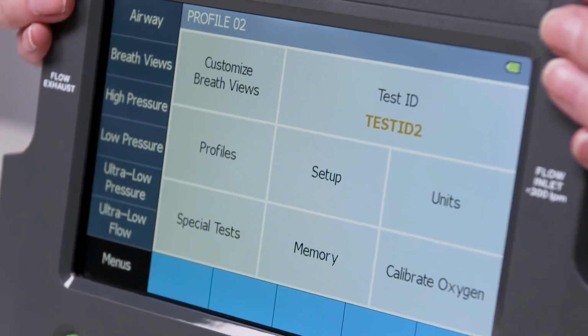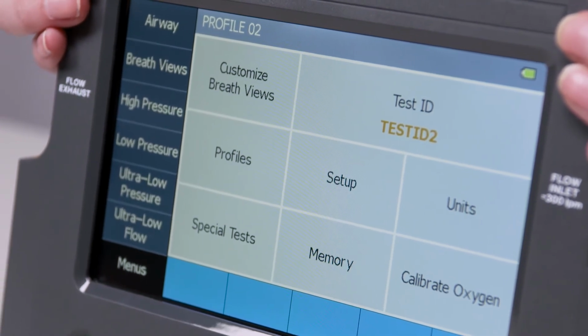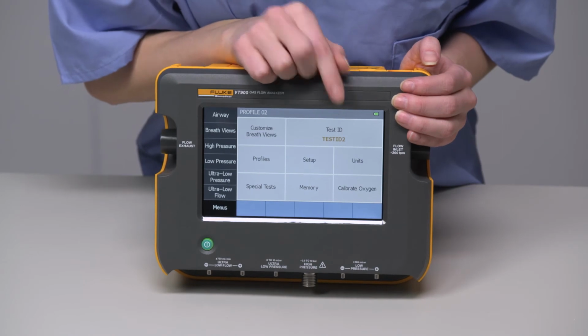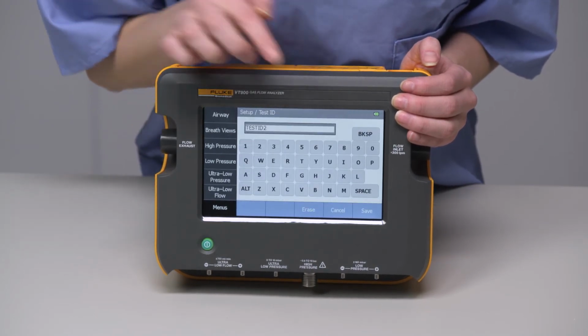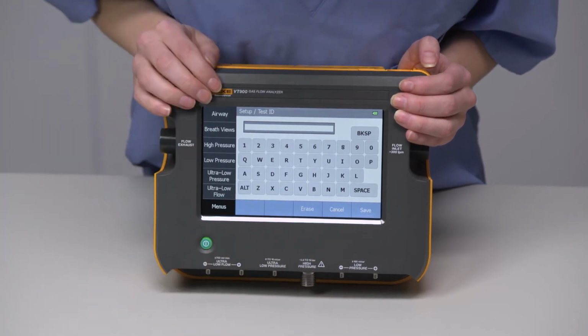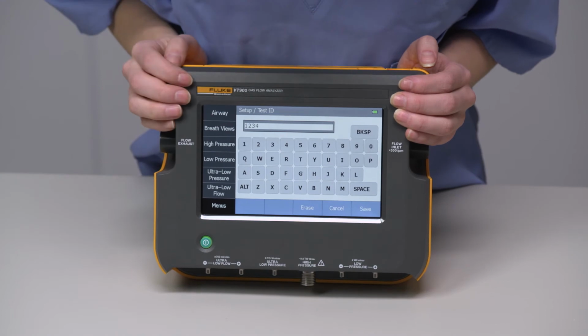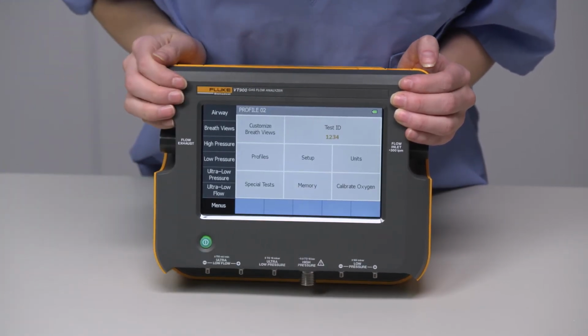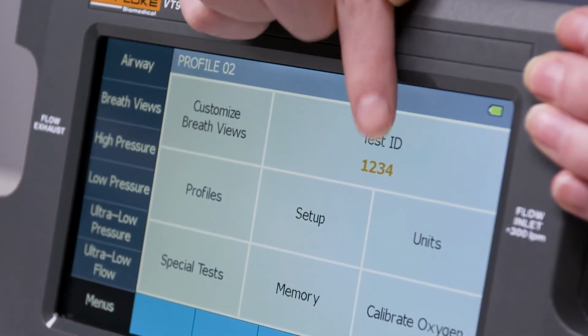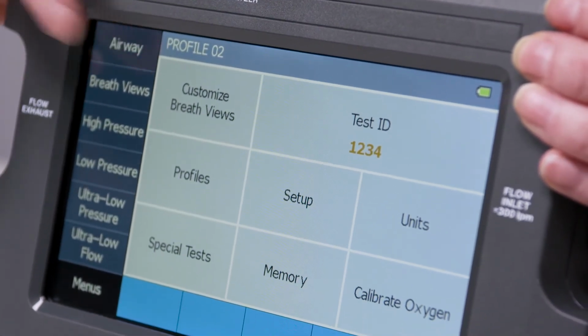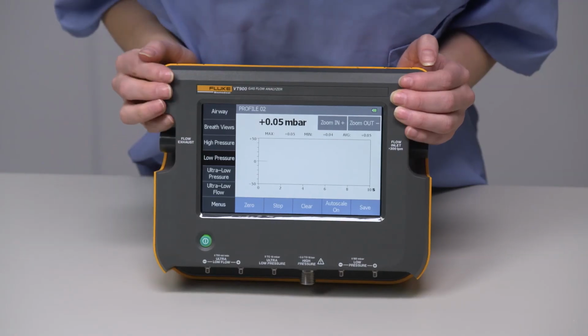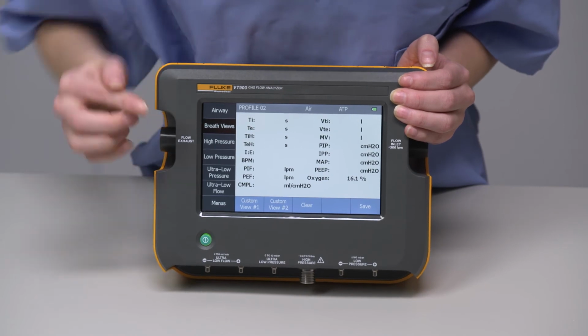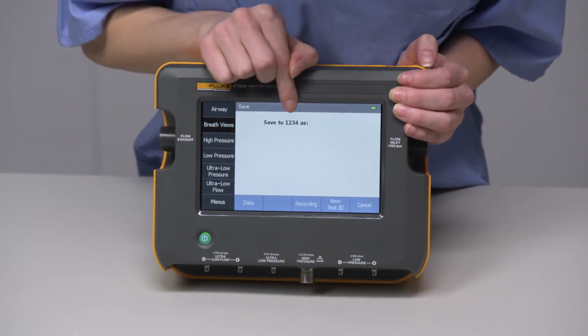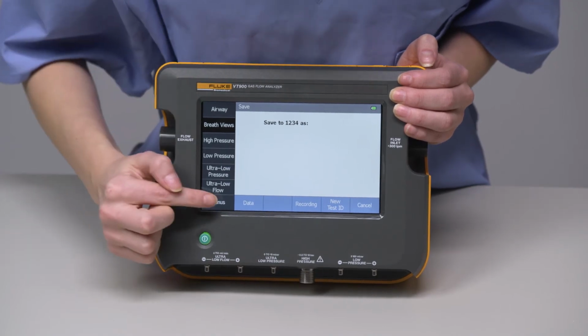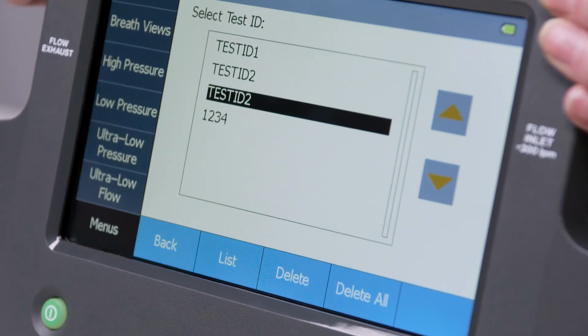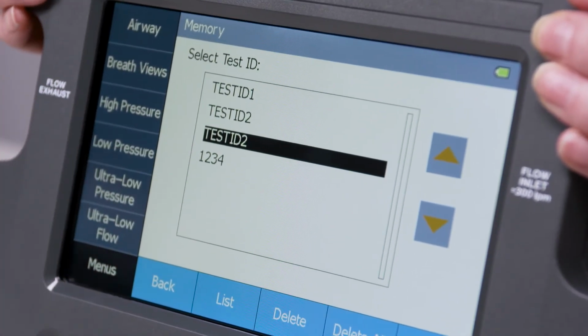The last thing we'll cover in the main menu, and one of the biggest highlights in the VT650 and VT900, is test IDs. If you're going to be saving data for reports, you'll want to set a test ID. A test ID can be many things, such as a device's asset number, for example. What it allows you to do is group data into one report. So, you could record airway channel data, low pressure, breath parameters, or whatever you need for your test procedure, and save it to one test ID. Then, when you transfer data to your PC, it will all be grouped together and be easily attached to your CMMS for that specific device.